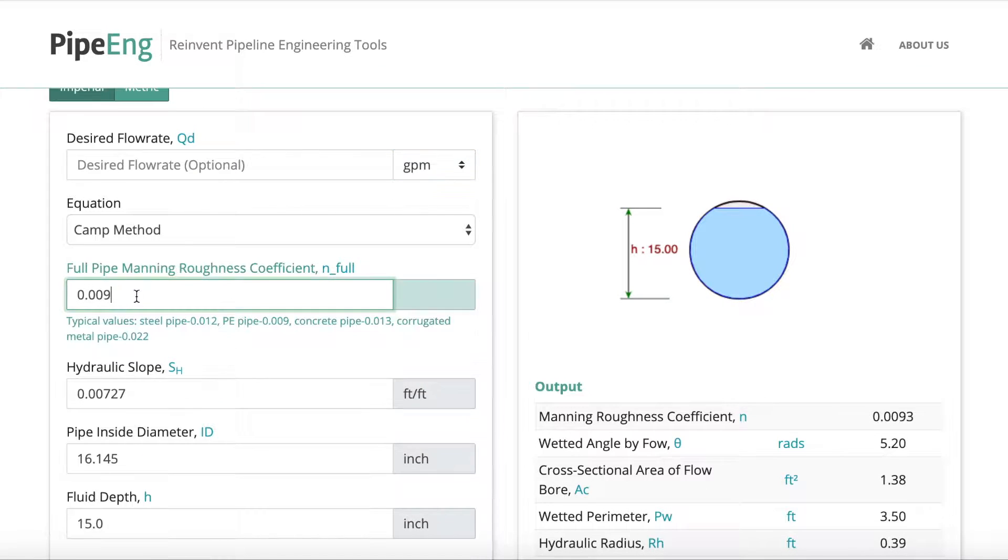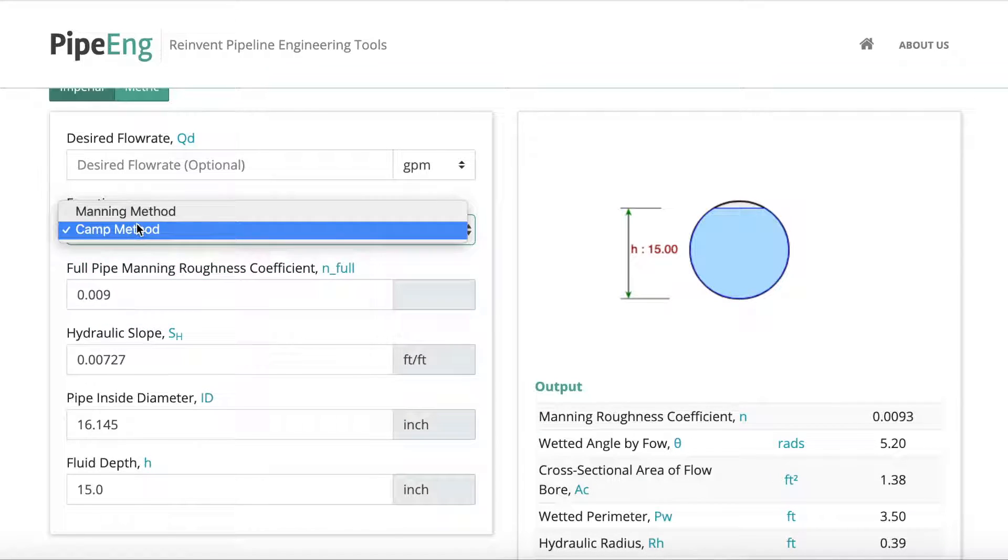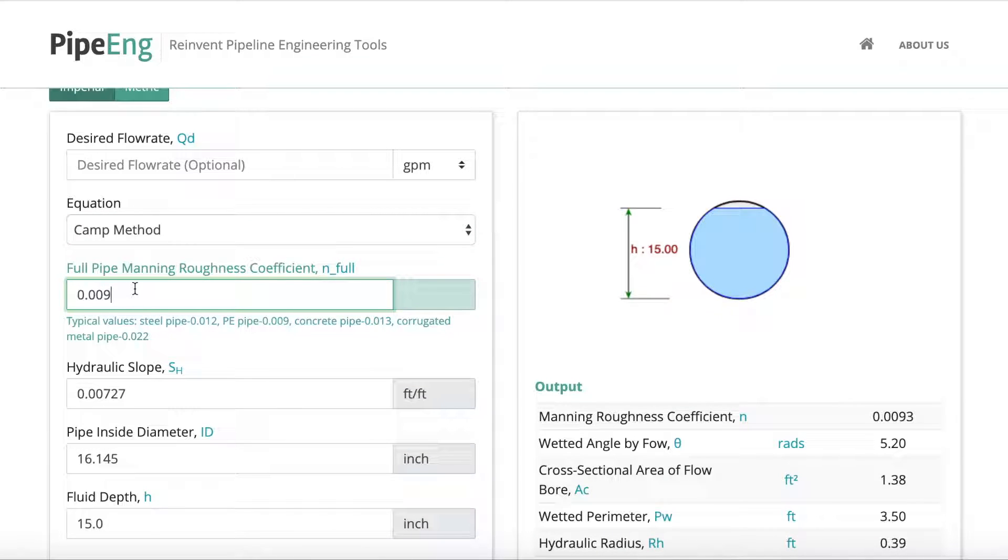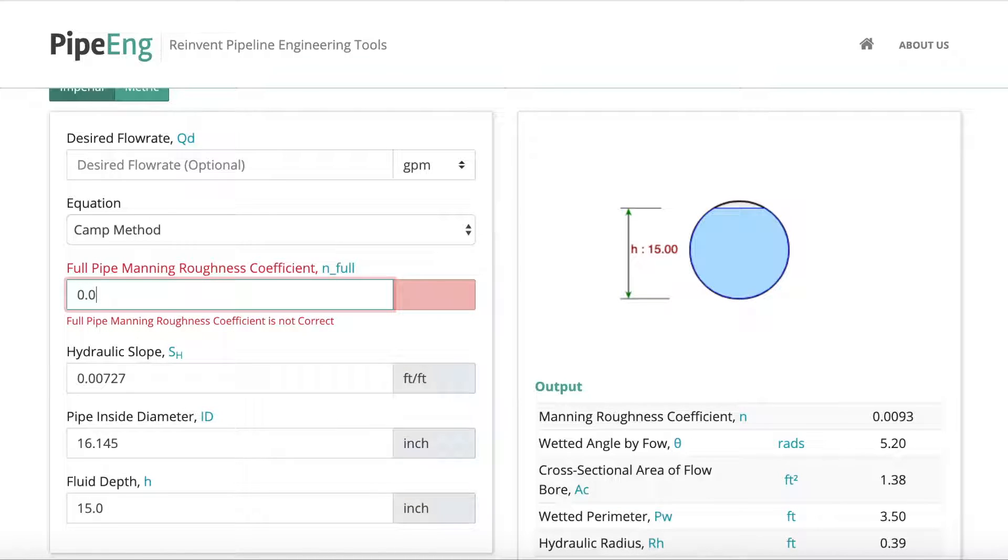So let's say you have, so the first here, this is for the second case. So the first thing you're going to choose is to use Manning method or Camp method. The next input is for full pipe Manning roughness coefficient. So we have some typical values you can use. The typical values depend on the type of the pipe. So in this case, let's say we have a steel pipe. So let's change this to 0.012.